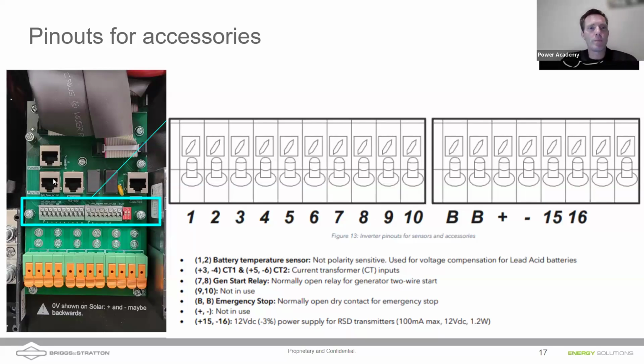You also have a pinout for accessories. So this is where you're going to wire in your CTs. This is where you'll wire, if you've got lead acid batteries, a temperature sensor. Or like most systems that are going in now, you'll have lithium batteries. You don't need that temperature sensor. You probably will have batteries like our 6.6 that have closed loop communications. And you'll get that information communicated directly between the battery and the inverter.